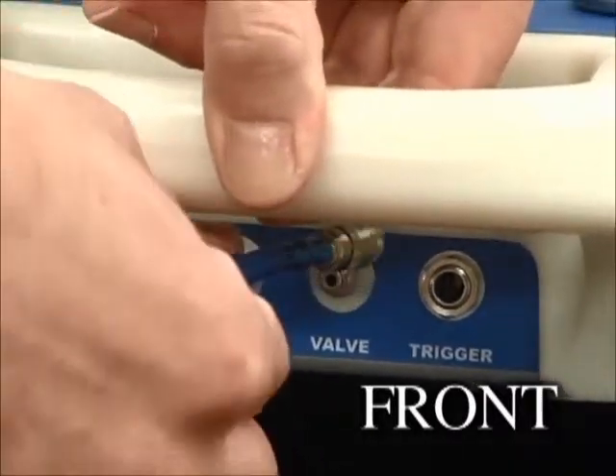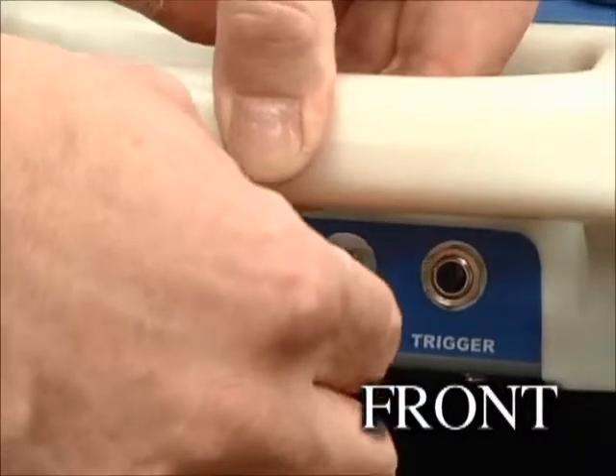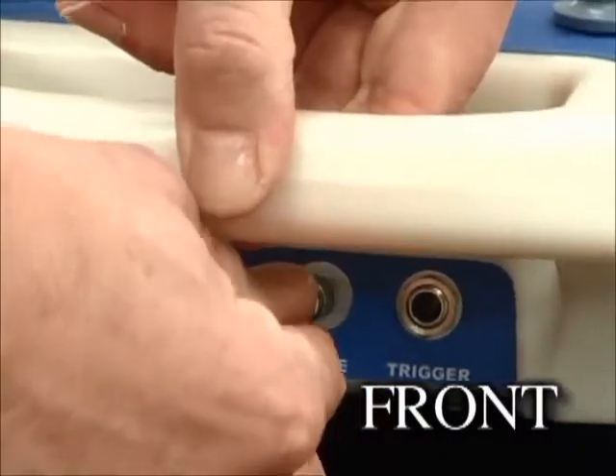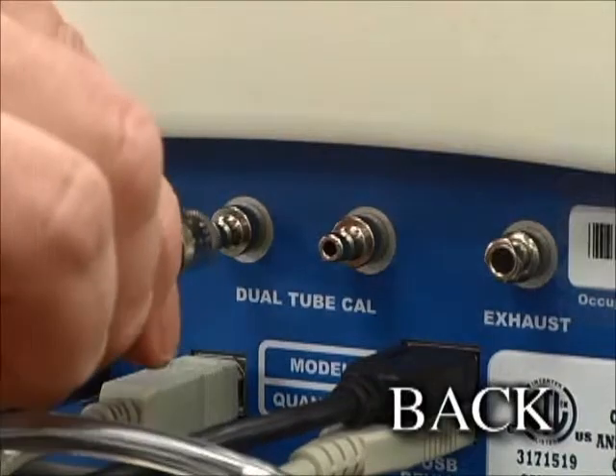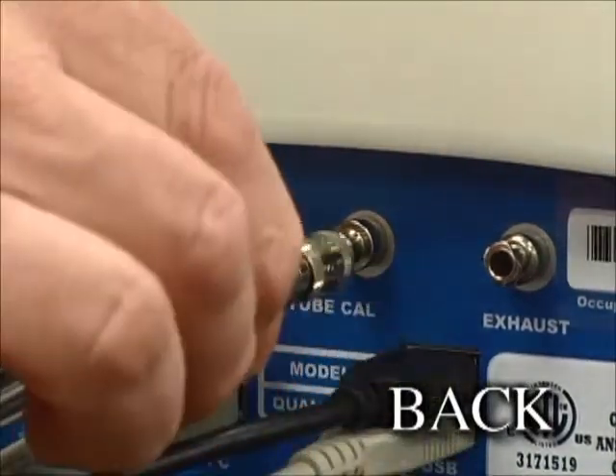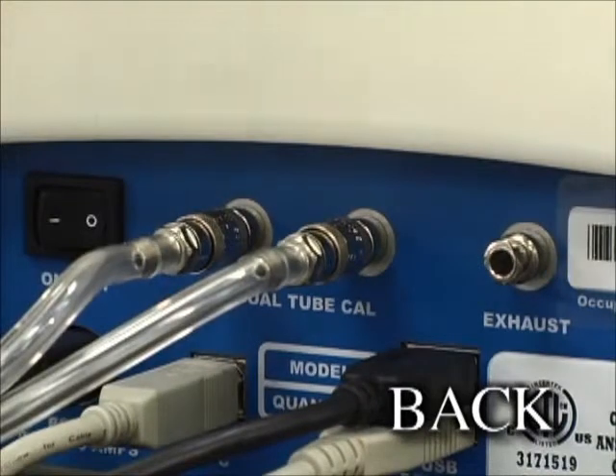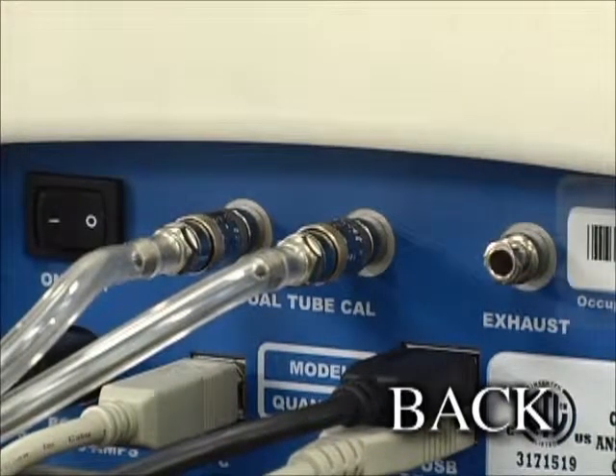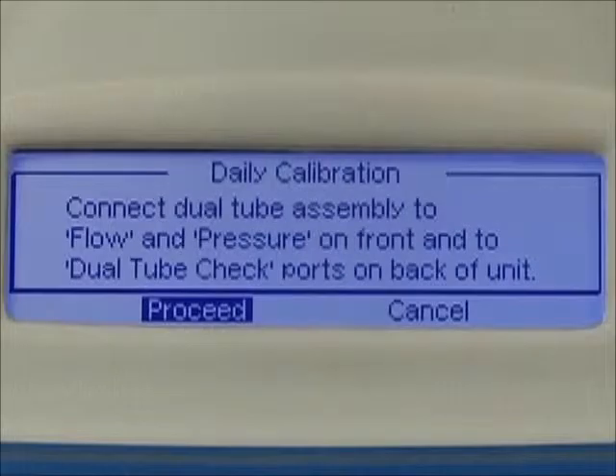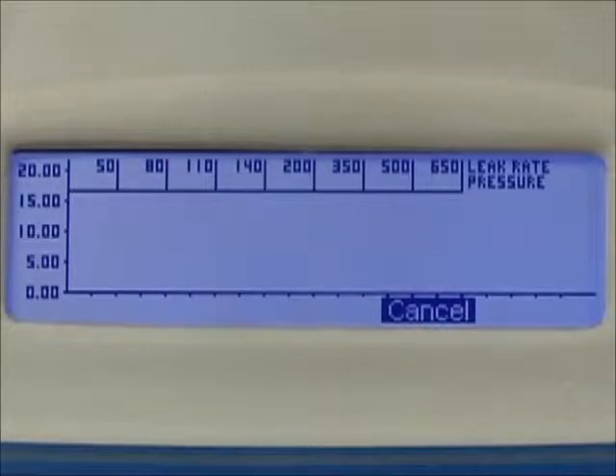Although not necessary for the calibration, you may want to connect the blue tube to the valve port at this time. Connect the opposite ends of the clear tubes to the dual tube cal ports on the back of the instrument. It does not matter which port you connect them to since they are interchangeable. Now you're ready to begin the calibration. Press the knob to begin the calibration. The dual tube calibration will run 8 different flow rates and will take approximately 1 minute to complete. This calibration confirms that the Quantifit is operating properly and within specification.